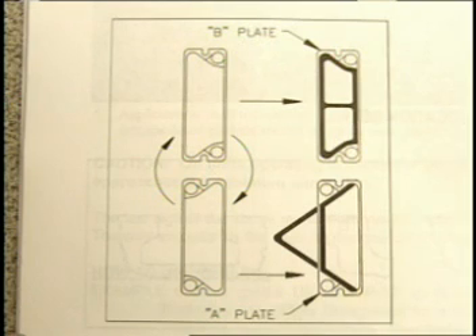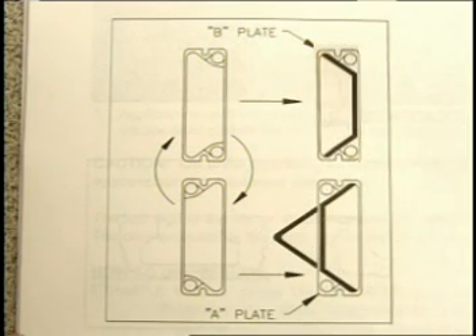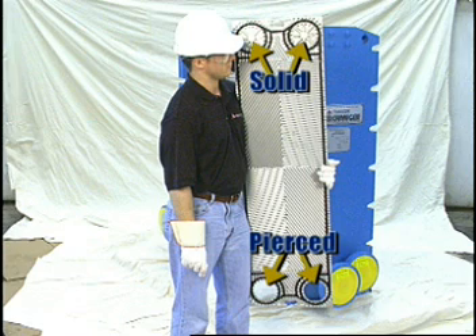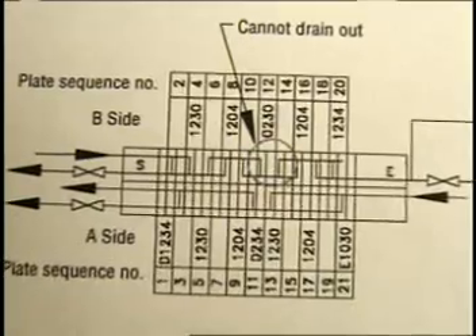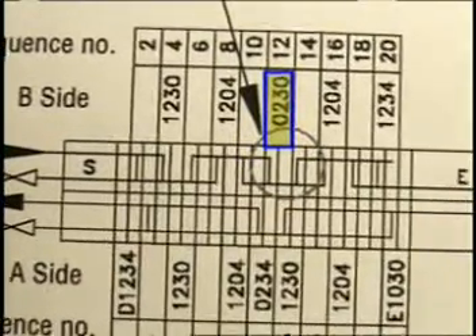You will see that an A-plate becomes a B-plate when it's rotated 180 degrees. For a plate with less than four portholes pierced, this will change the plate's designation. For example, this is a 0230 plate. Looking at the element composition diagram shown in Figure 16 of the installation manual, this plate must be located in position number 12 for proper heat exchanger performance.